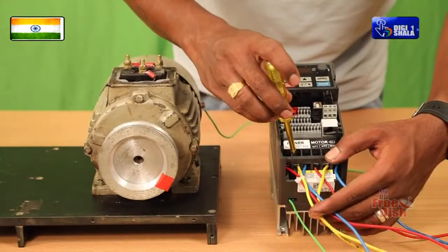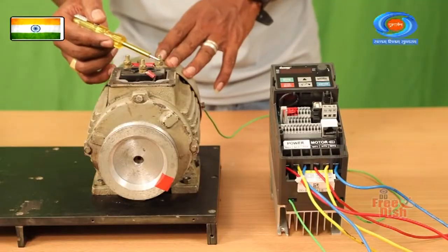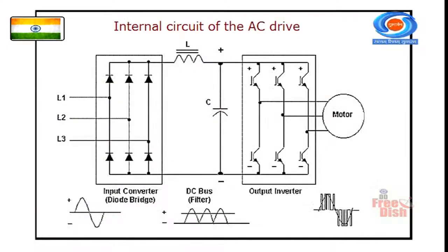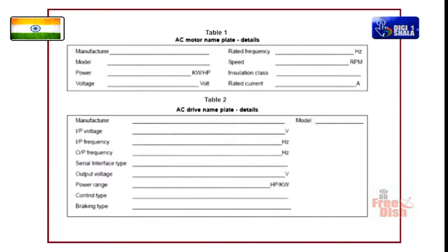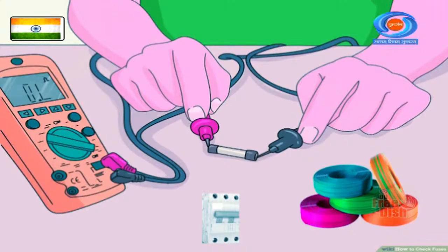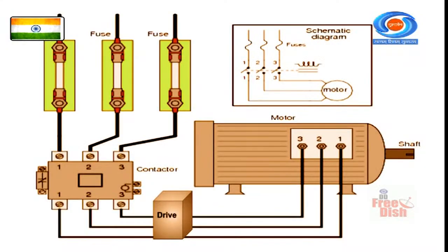Identify terminals. Identify the input and output terminals on both the AC drive and the AC motor. Identify and trace the internal circuit of the AC drive. Note down the nameplate details of the given motor and AC drive and enter them in Table 1 and 2. Check the switch or MCB, cables and fuse wire rating and match with motor rating. Draw the connection diagram of the AC drive motor.